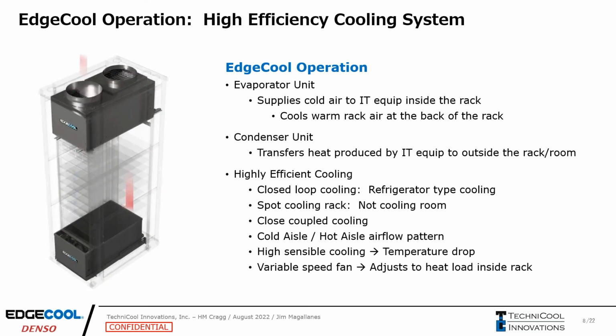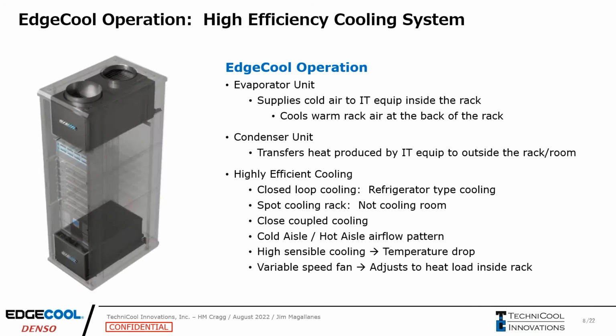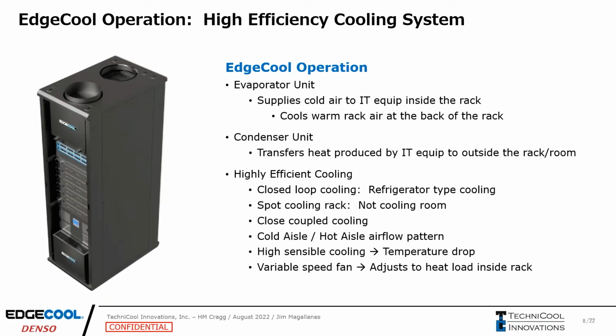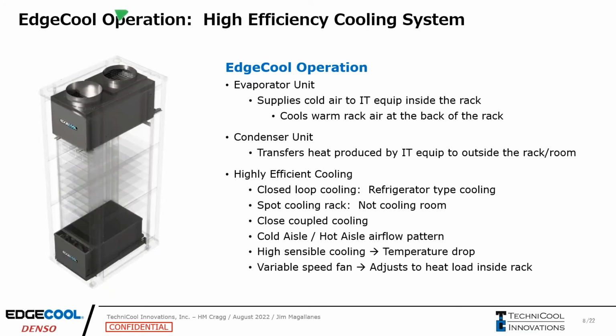Next is the close coupled cooling. We're actually bringing cooling directly to the heat source. So you can think of the larger data centers where they have the perimeter cooling, that raised flooring where they blow the cold air underneath the flooring, and it pops up through the floor tiles in front of the racks. There's lots of different places where that warm air and cold air will mix, and it's not very efficient. Also, the ceiling, the mini split air conditioner, you have that on the wall and you're blowing cold air in, and you're just mixing that cold air with hot air. And again, it's not really an efficient way to cool it down.